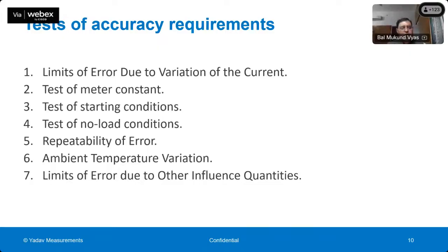Then all of you must have seen that there is an LED on the smart meter or electronic meter, which keeps on blinking. What is that LED? That LED is actually a pulse output which is used for testing the accuracy of the meter. So if you are consuming more load, the LED will blink faster. If there is no load, then the LED will not blink. And if there is less load, then the LED will blink slowly. So the speed of the LED is proportional to your power consumption or electricity consumption. And there is a meter constant written in the unit of impulse per kWh or impulse per kVArh on the rating plate of the meter. The accuracy of that meter constant has to be tested, which is very important because that is used for accuracy testing of the meter. So there is a test for testing the accuracy of the meter constant.